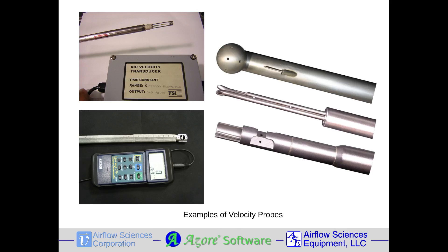There are a variety of probes used for flow measurement in gas streams, including hot wire (upper left), vane anemometer (lower left), and pressure differential or pitot probes (right). For industrial applications, the S-type pitot probe (middle right) is widely used because its large pressure ports make it resistant to pluggage from moist or particulate-laden flow streams.